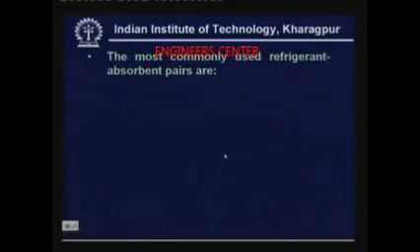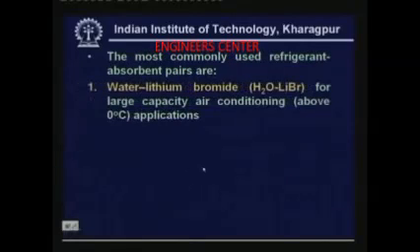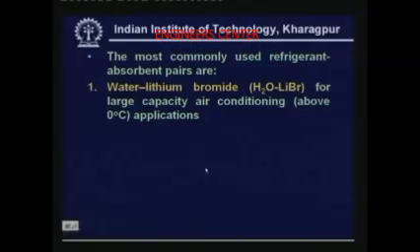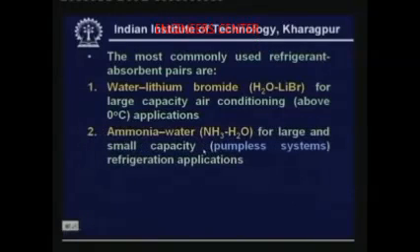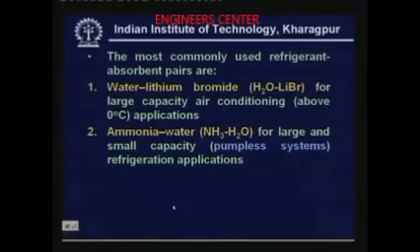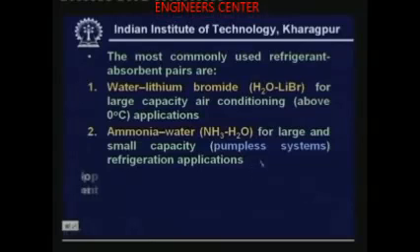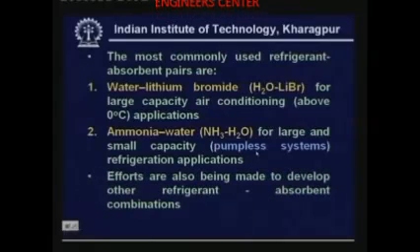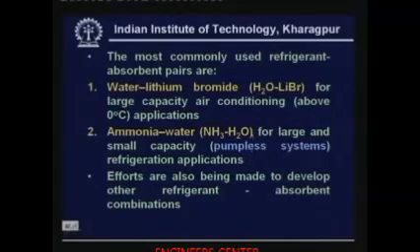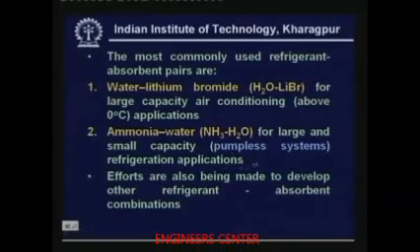Based on these desirable properties, the two most commonly used refrigerant-absorbent pairs are water-lithium bromide for large capacity air conditioning applications, and ammonia-water for large and small capacity refrigeration applications. These will be discussed in detail in the next one or two lectures. Other refrigerant-absorbent pairs exist at the research level but are not yet commercialized.